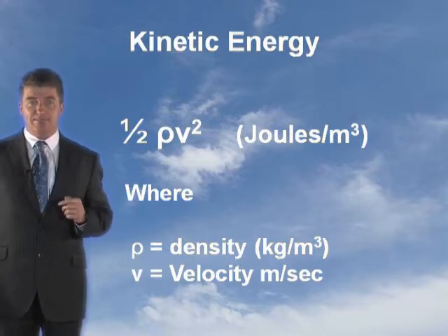That's the kinetic energy. And then finally, the third type of energy is pressure energy. The pressure energy is due to being under pressure. Now, the SI unit of pressure is the Pascal. But in the fire service, they use the bar or metres head. They're still used. Therefore, there are three forms of the pressure energy. And when working with this calculation, you've got to select the form of pressure energy relating to the question.